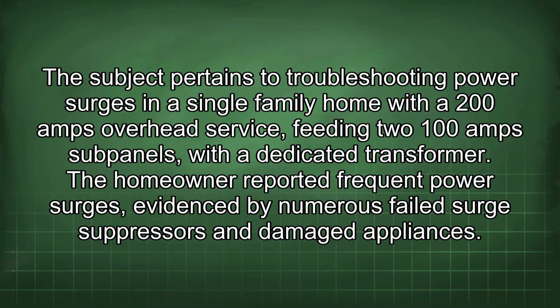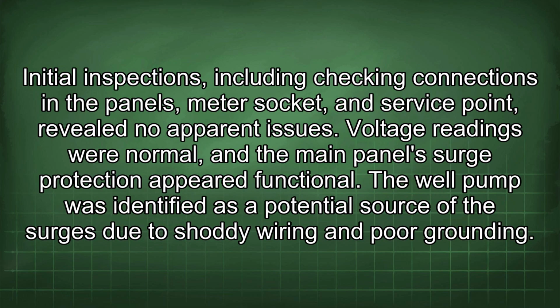The subject pertains to troubleshooting power surges in a single-family home with a 200 amps overhead service, feeding two 100 amps sub-panels with a dedicated transformer. The homeowner reported frequent power surges, evidenced by numerous failed surge suppressors and damaged appliances. Initial inspections, including checking connections in the panels, meter socket, and service point, revealed no apparent issues.